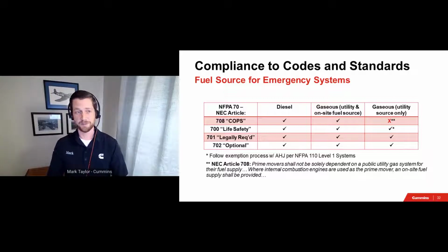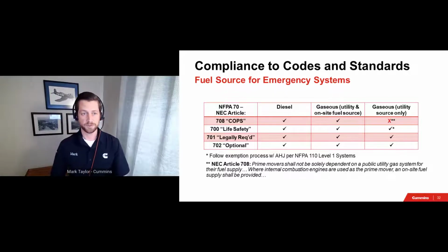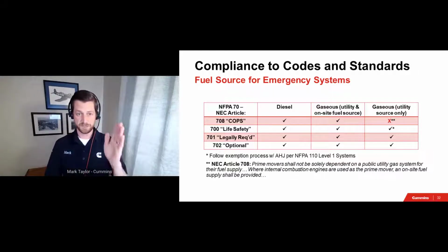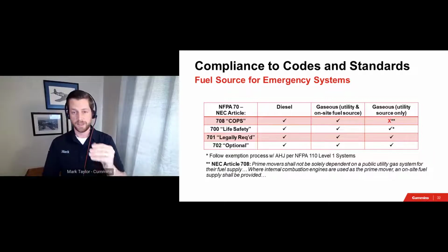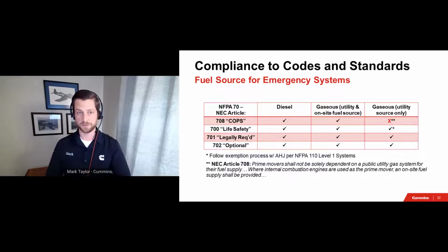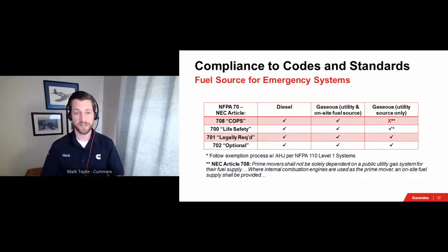I have this table here in an attempt to best summarize on-site fuel storage requirements, whether it's diesel or gaseous fuel. Looking at the rows, covering the different articles of the NEC, and the columns for diesel, which is inherently an on-site fuel, gaseous fuels, whether it is utility only, and differentiating it from on-site storage. Of course, a gaseous generator set with on-site fuel will meet those requirements, same as diesel, so long as that storage is appropriately sized, of course.